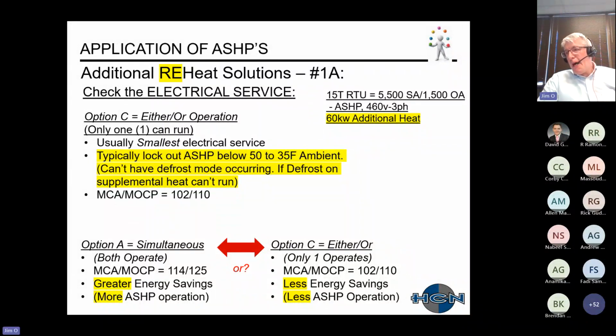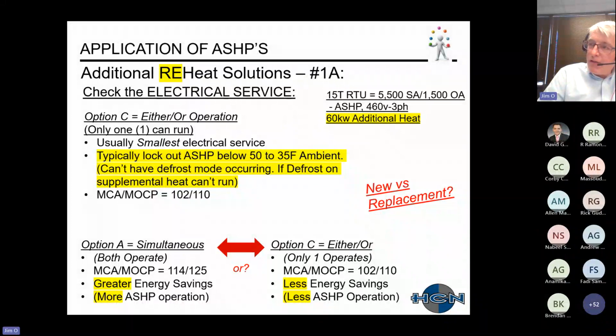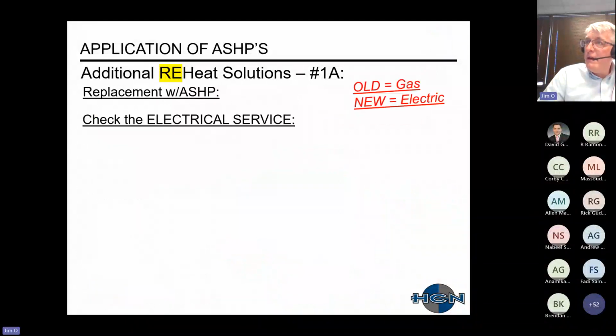The simultaneous option typically has greater energy savings because you're running the air source heat pump more than you would in the other scenario. A lot of times this is very dependent on whether it's a new project versus a replacement. I would say that for new projects, we end up doing simultaneous heating all the time. And for replacements, it's not 50-50. Once again, it's probably mostly simultaneous, but there are situations where the electrical service becomes critical.